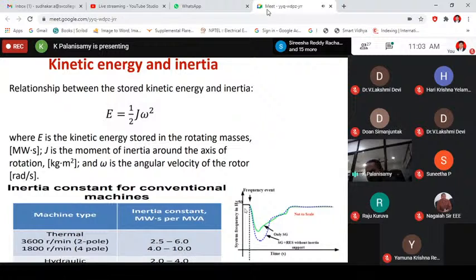Since you are decoupling, it means you are isolating the mechanical devices from the inverter or from the grid. So there is no contribution of inertia from the windmill. Of course, the windmill has a big rotating mass, but it cannot contribute, because your power converter is in between. So when there is a fault, the rate of change of frequency is very high.